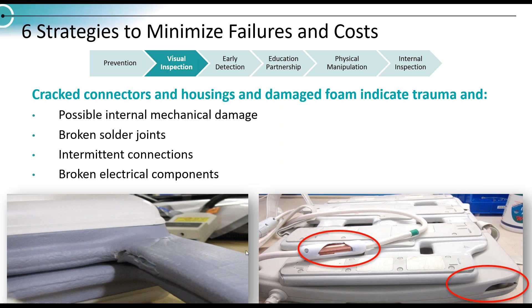Here are a couple of failures that didn't occur overnight. This is a coil sheathing failure that has occurred probably over months of continued flexing. The outer sheathing has been compromised, but if left much further, damage to the individual wires will occur, and then all of the wires will have to be replaced as part of a repair. We're talking hundreds of dollars versus thousands of dollars if we address these things when we see a tiny tear to the foam or sheathing, versus a breaking of the wires in the wiring harnesses themselves.